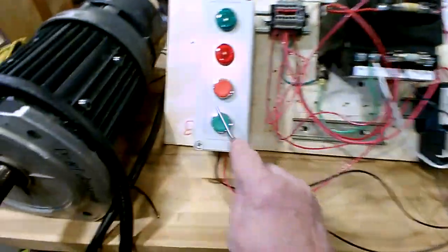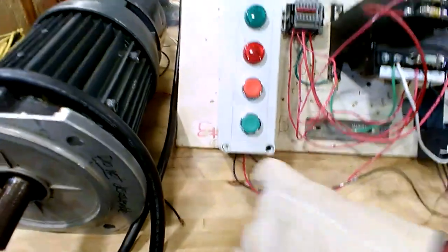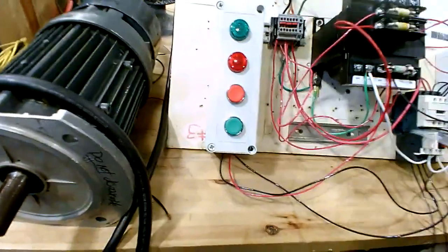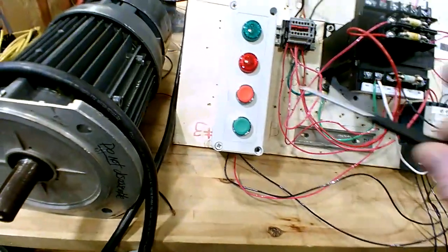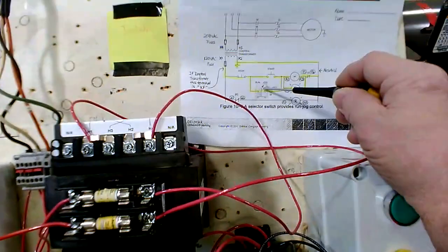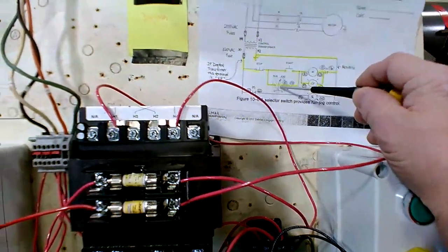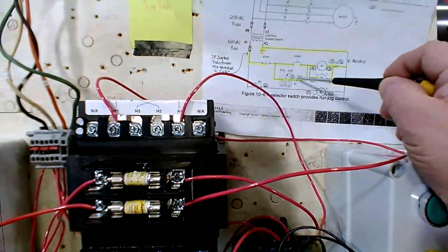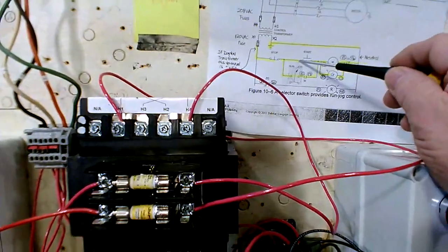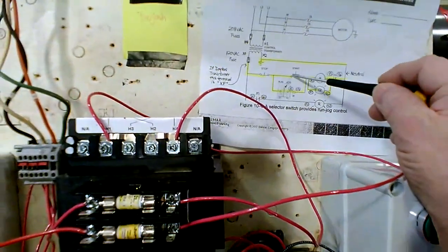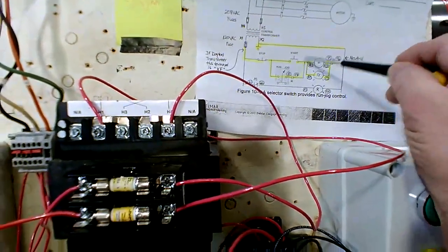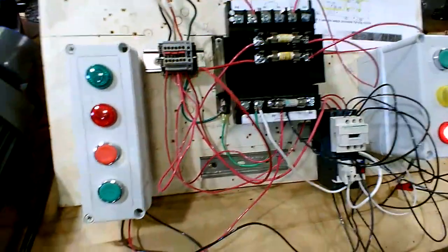Now it's only going to run when you bump it with the jog button. So just bump it. It'll make it bump like a conveyor. It can make the conveyor move a little bit if you're going to move the product a little bit and then stop. That's a jog feature there. What you've done with that switch is you're actually opening up the holding contact. You cut power from 13 so it can't hold down. So you're going to be a straight circuit here momentarily. That's what you would do.